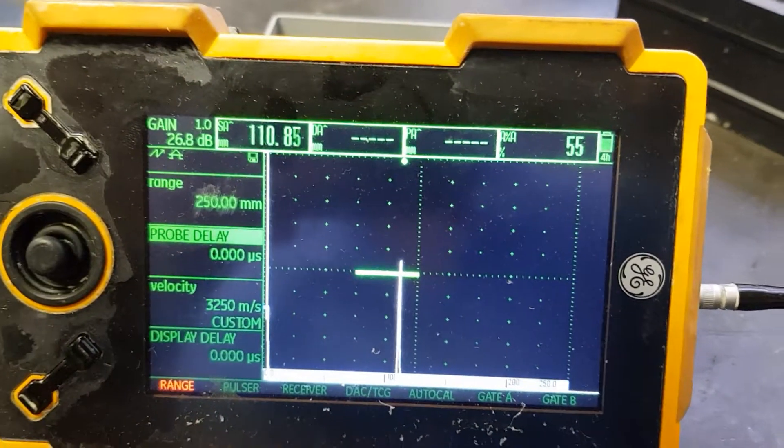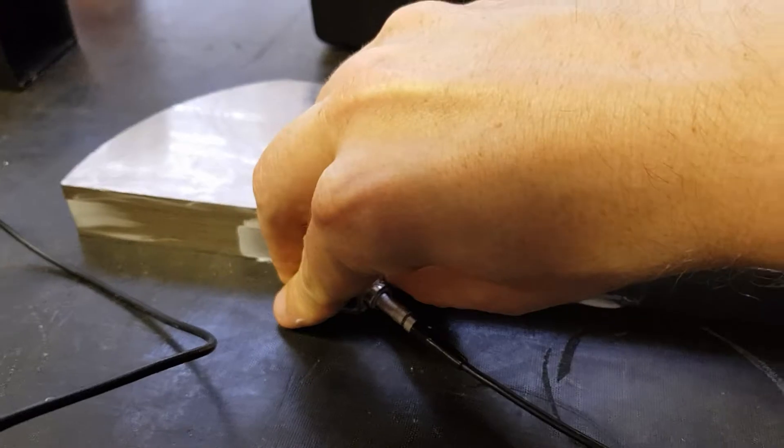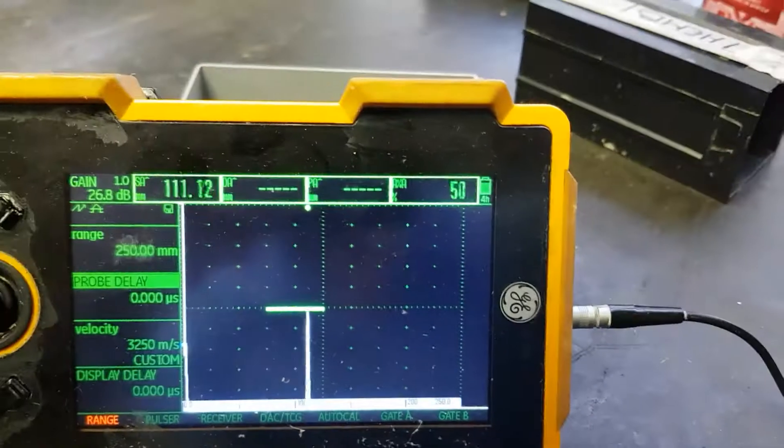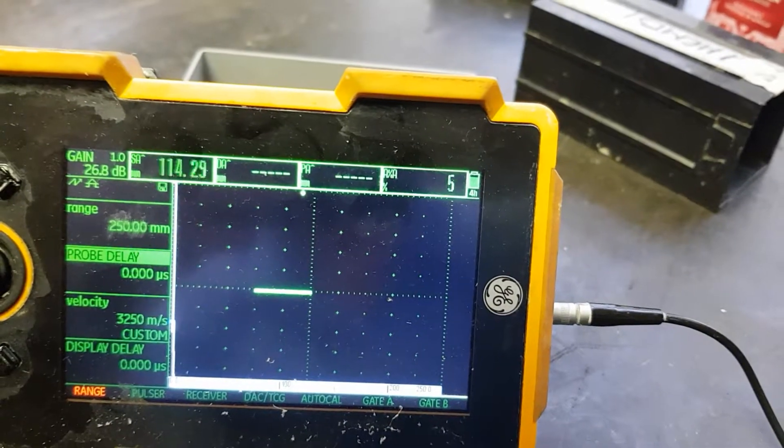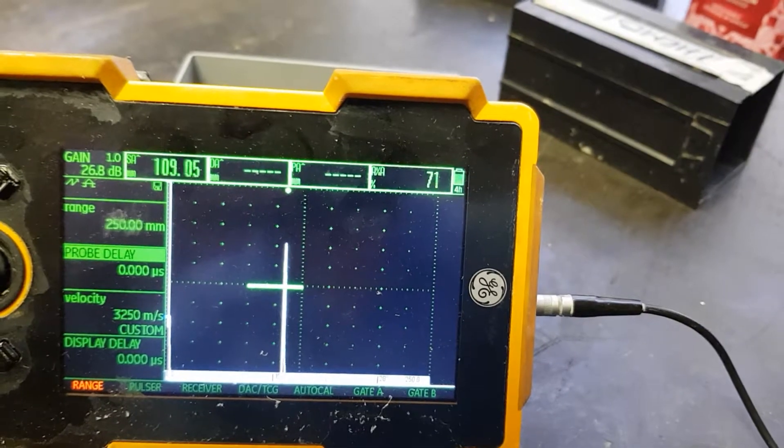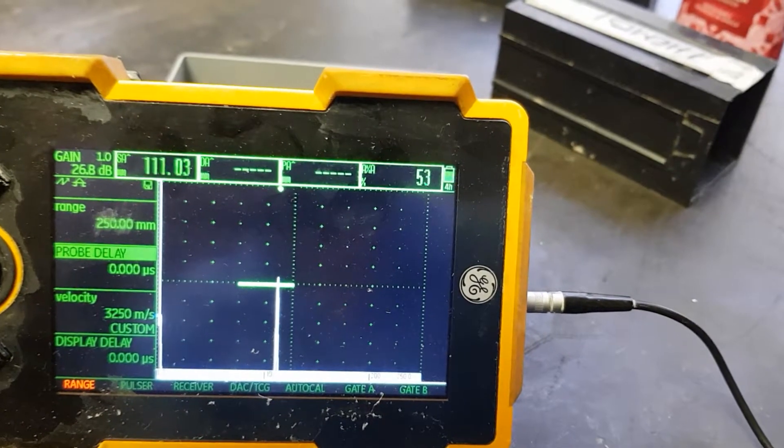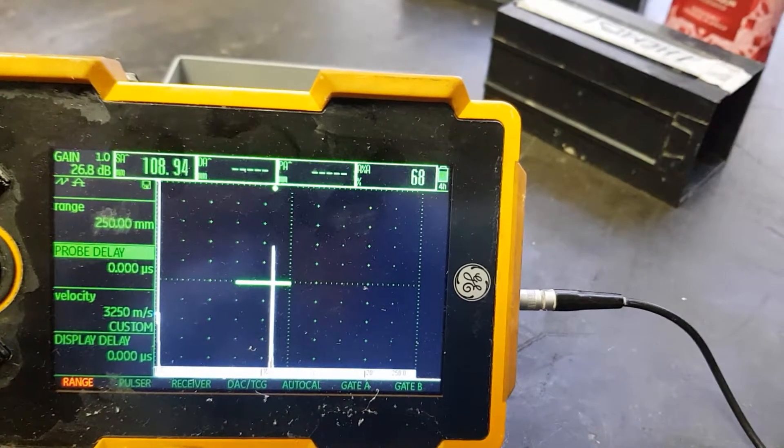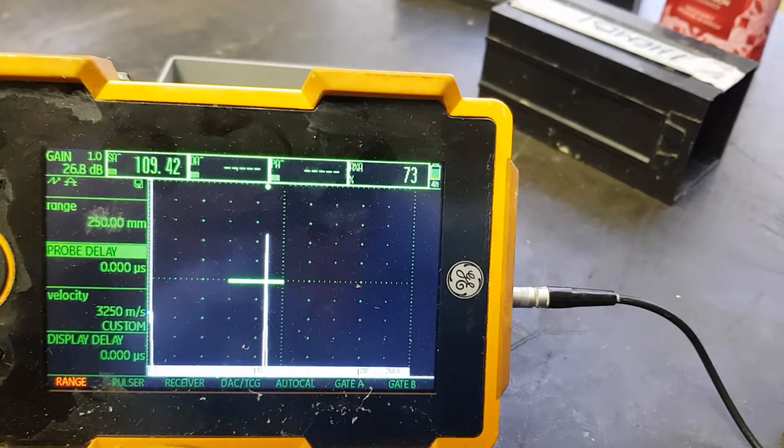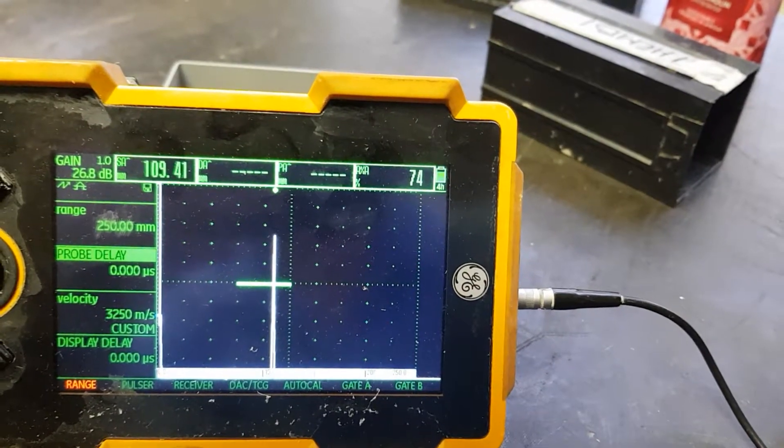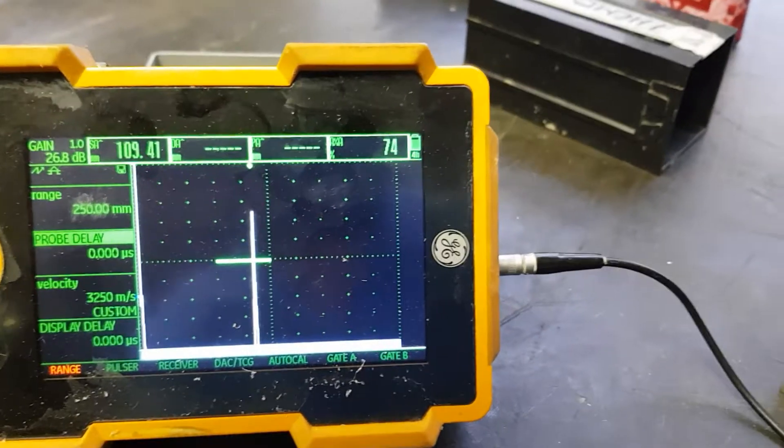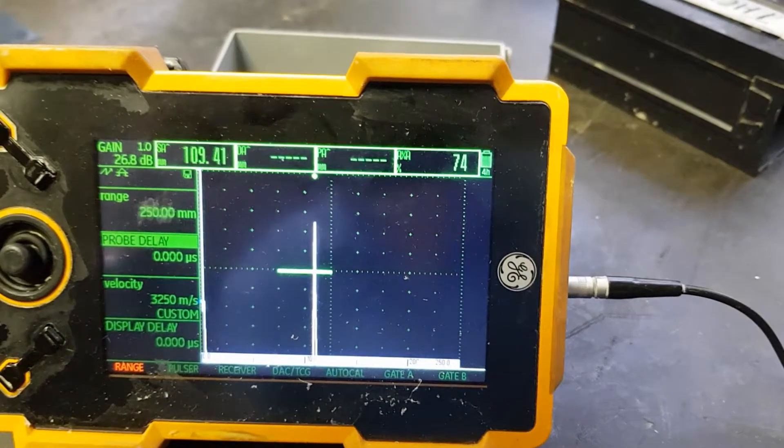We move the probe forwards and backwards on the V1 block until the echo reaches its maximum. We can see it goes up, reaches a maximum, and then comes down again. The idea is to stop the probe where this maximum is reached.